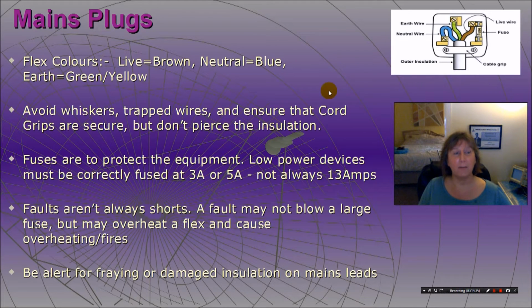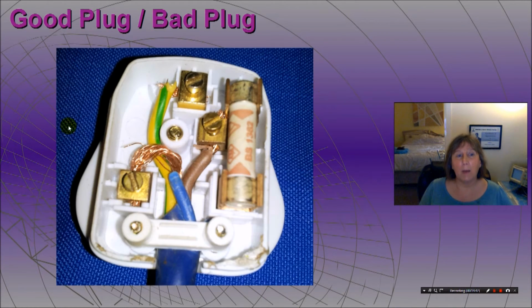So, a good plug and a bad plug - let's look at a couple of examples. Here's a plug where the insulation isn't quite fully inside, and the plastic piece screwed down to hold it won't give a very secure grip. Ideally the insulation needs to go up into this area so you know there's a good grip.